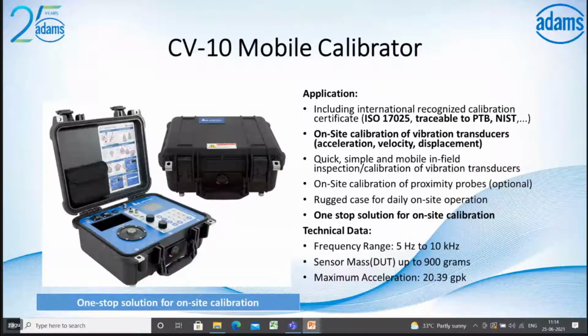CV10 mobile calibrator. So this is specially designed for the on-field calibration of vibration transducers. And it's a one-stop solution for on-site calibration from the frequency range 5 Hz to 10 kHz. And the maximum acceleration you can go up to is 20 g peak, and you can vary the acceleration and frequency during the measurements. I just want to show you some functionality and features of CV10.